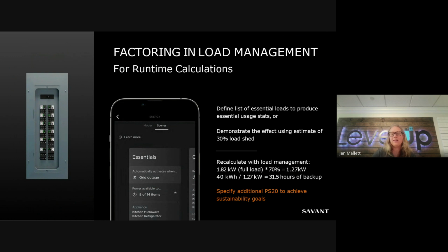So if we do that, let's take the previous scenario and recalculate what our uptime is with load management. We're looking at 1.82 kilowatts, which is the full load, times 70%. That's what we want. So we want a 1.27 kilowatt energy consumption there. In that case, we're upping our backup time from the 22 hours, because we've shed 30% of the load, to 31.5 hours of backup. So that's some of the powerful things that can be created and designed with systems like this versus traditional energy, whether it be solar coming in or generators. It's really about how you take this energy and maximize its output for the person in the house.